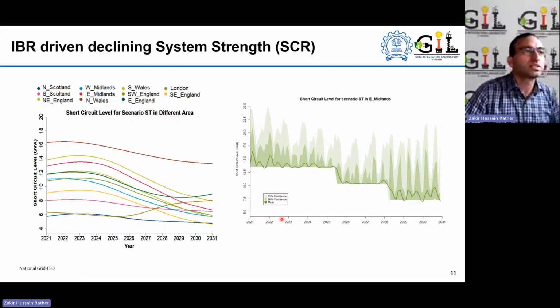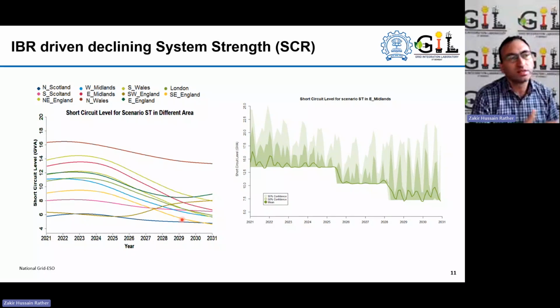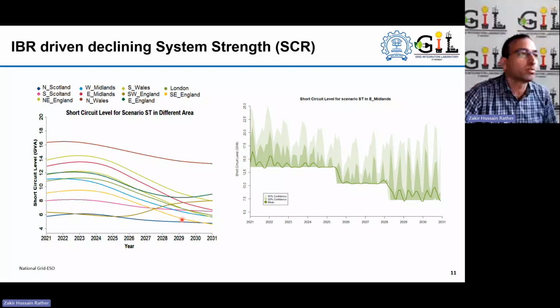Similarly, grid strength is also getting impacted, as you can see here. In one of the case studies on a grid, the short circuit level is broadly, of course, dependent on the generation mix in a given control area or area of focus. But in general, with the increase in renewables and the displacement of the rotating mass in conventional generators, the short circuit capability of the system is broadly deteriorating, and that is the other side of the impact. These are just a couple of impacts, to show that IBRs introduce technical challenges that make it challenging for grid operators to handle grid operation under high penetration of renewables.